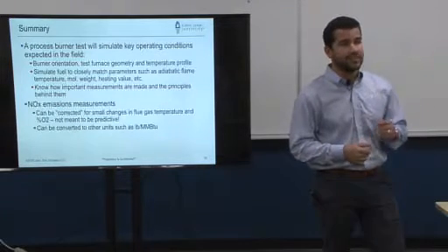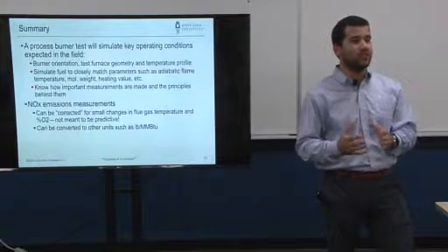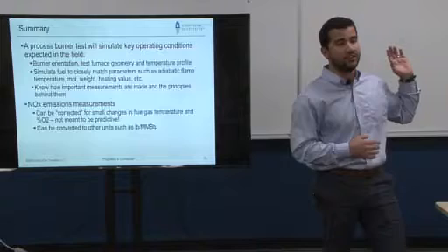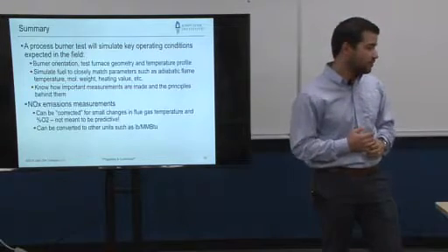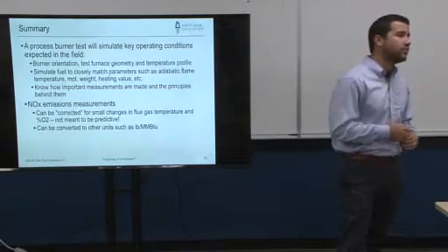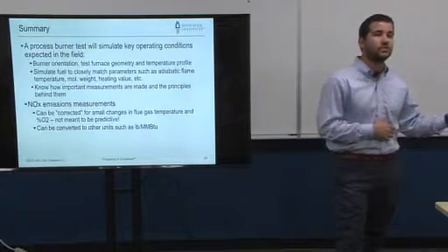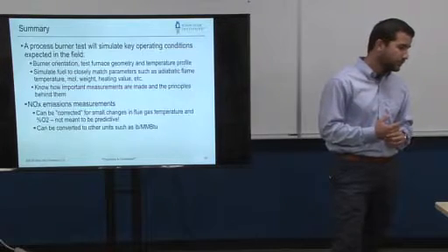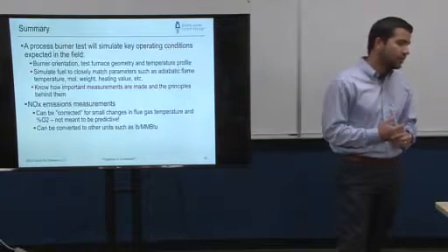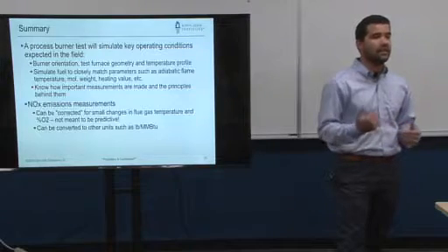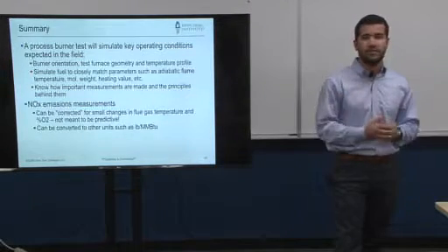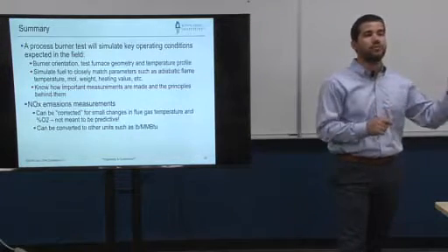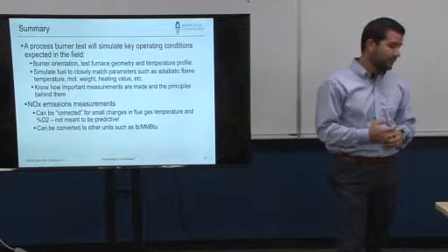It's a lot easier to fix the issue on one burner in a tiny heater in Tulsa, Oklahoma, than it is to fix it in the middle of Nebraska on 325 burners. So it's very important for you to be honest with yourself and really understand what it is that you're about to do and how you can simulate that pretty much in your backyard, if you will. And really understand what you're measuring. The fact that you get a temperature that says 1500 degrees doesn't mean that you have matched everything. You've got to understand where that sits in the final process and what it really means.